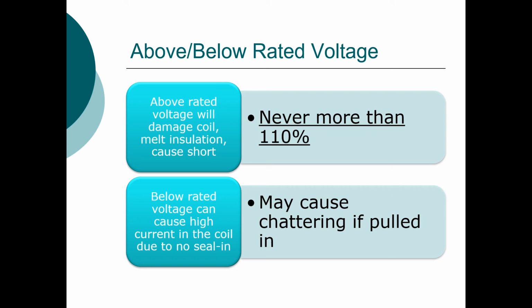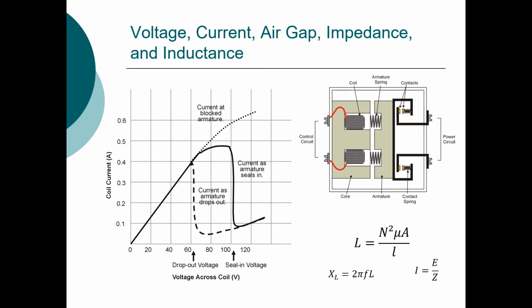The reason the current is so high right before the armature seals in is all about inductance. As we remember from our theory, inductance is increased when my magnetic path is also increased. Inside my contactor, I have an air gap between my core and my armature. And when I eliminate that air gap, I complete my magnetic path, which will increase my impedance, which will also increase my inductive reactance. Since my inductive reactance goes up, my current will go down after the armature seals in.